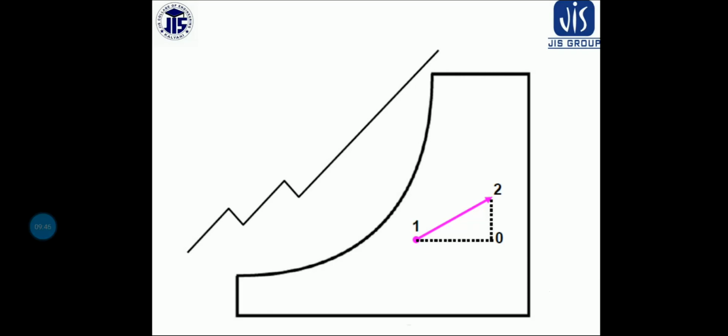In such a process, the air increases in specific humidity and enthalpy, and the dry bulb temperature will increase or decrease according to the initial temperature of the air and that of the spray. If sufficient water is supplied relative to the mass flow of air, the air will approach saturation at water temperature. In this figure, it is 1 to 2 that is denoted.